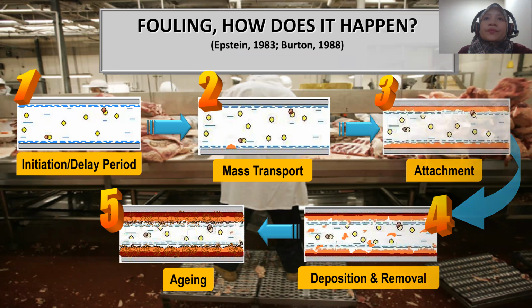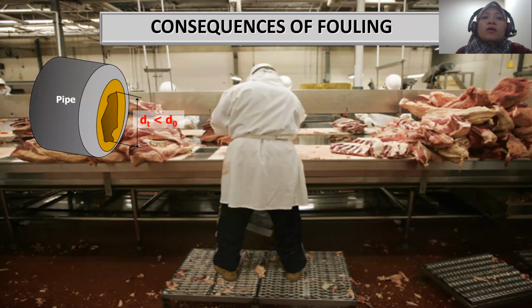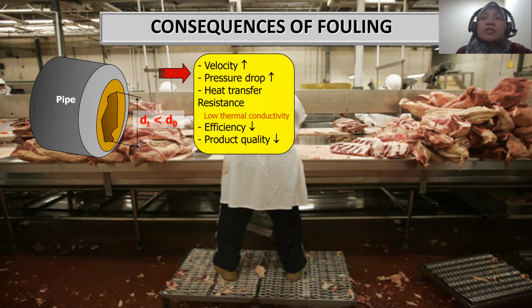Let's see the impact of fouling deposit on the processing industry. When fouling deposit starts to build up, the plant surface will become resistant to heat transfer. We know that food has low thermal conductivity. When fouling thickness increases, velocity of processing fluid will increase too, causing a pressure drop. Then, of course, fouling deposit could reduce the product quality.